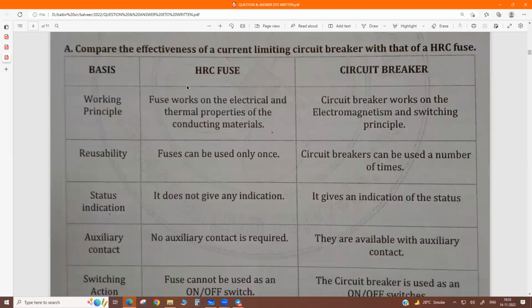So there is a comparison between the HRC fuse and the circuit breaker. Actually the circuit breaker is fast acting, because it senses the fault and interrupts, and the fuse also. Fuse means fuse wire, okay? So the fuse senses high current, overload current. Basically this fuse provides short circuit current protection, not overload, only short circuit. But the circuit breaker provides short circuit, earth fault and overload protection also. And the operating principle of the fuse is Joule's heating principle, depending on I squared R t.